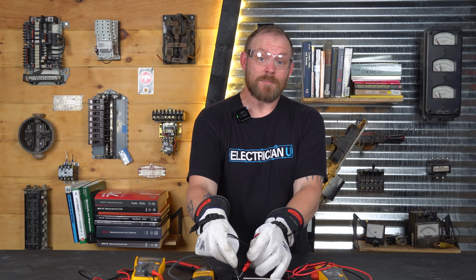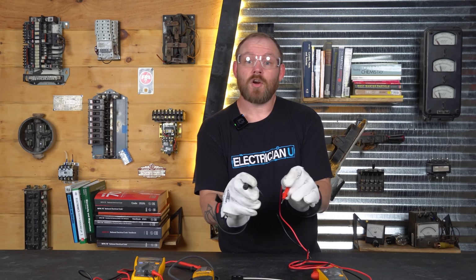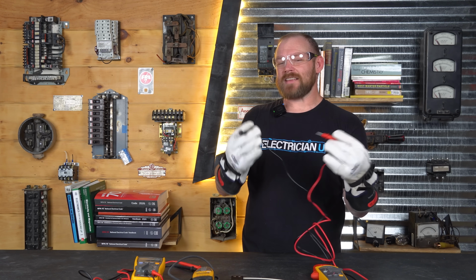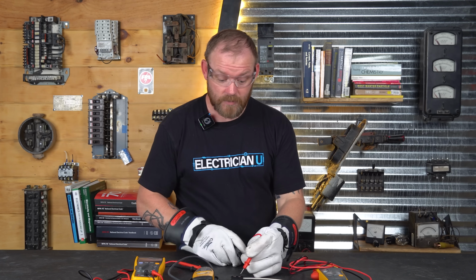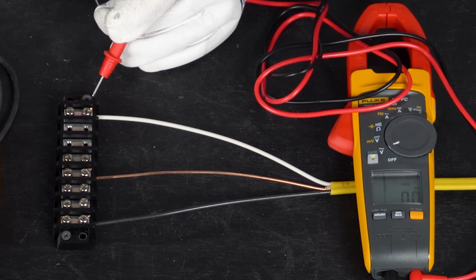There is a difference of potential, which is why the multimeter is seeing it. There's a small shift in current, small enough to be perceivable by the multimeter, but because the impedance is so high, it can't really decipher whether or not there's any power behind that. So if I were to connect a vacuum cleaner or something between this white and this bare conductor, it wouldn't turn on.